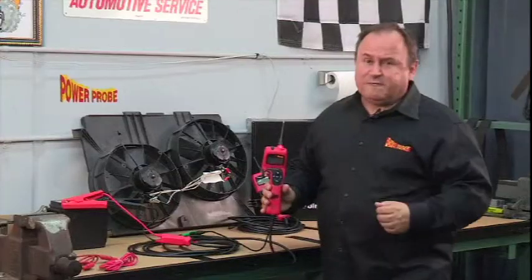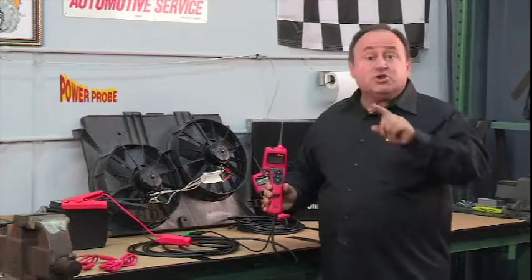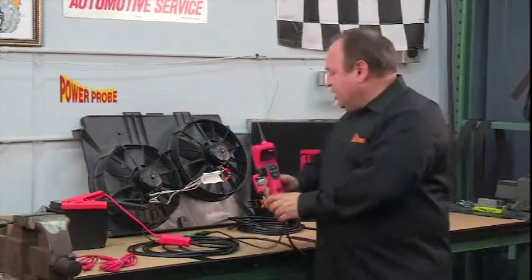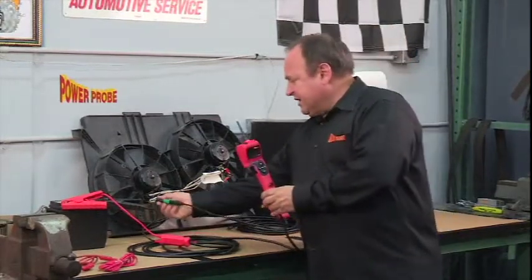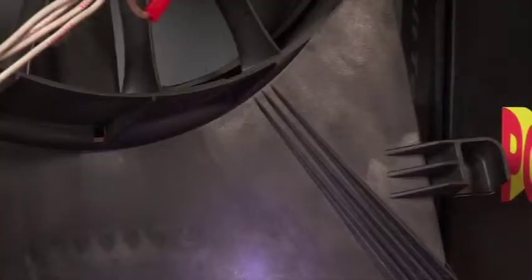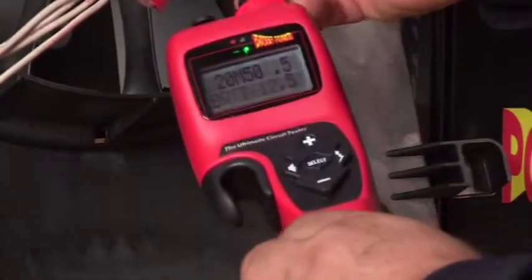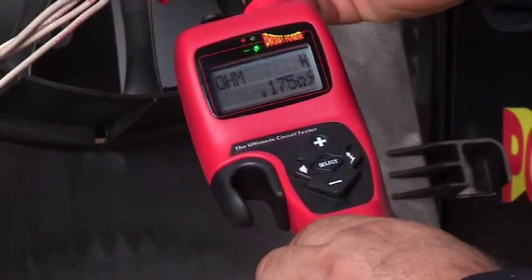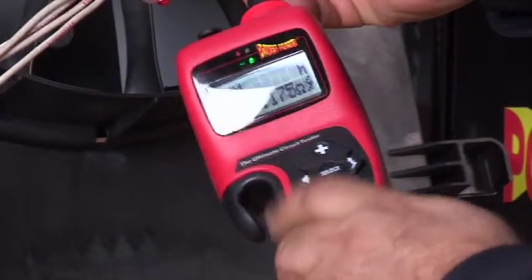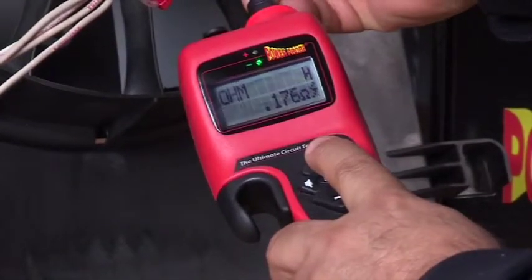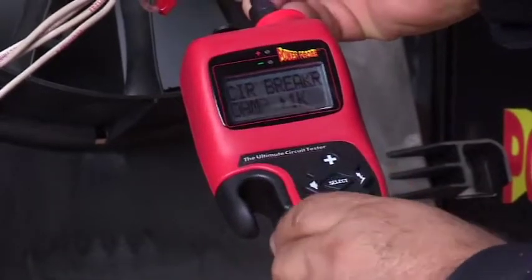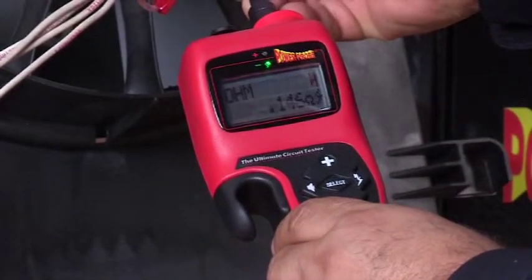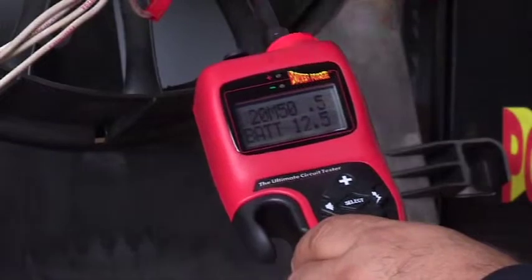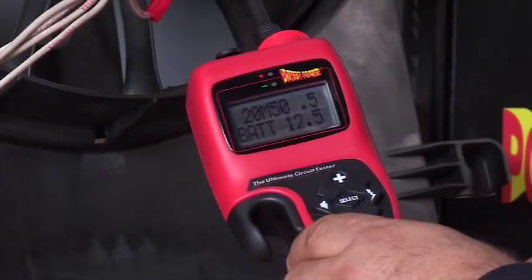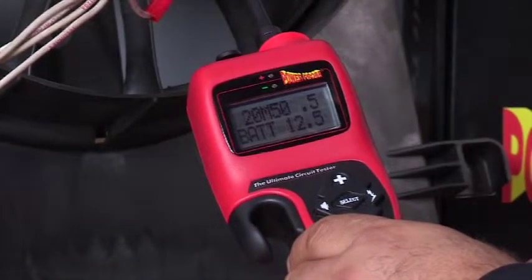Here's another powerful feature that breaks barriers. Check this out. Let's connect the auxiliary ground lead to the negative side of these fans. As we probe the fan motors, you can read passive resistance of the motor windings. But watch what happens when I press the power switch to activate it. The PowerProbe Hook just exceeded the 20 amp circuit breaker setting. That's not a problem. Let's just set the circuit breaker to 65 amps.